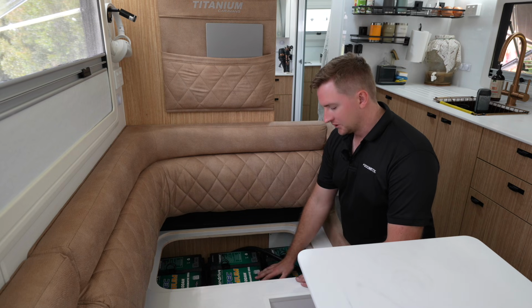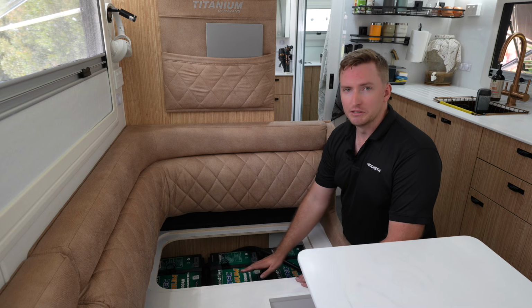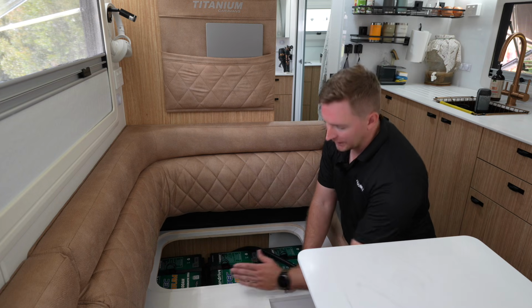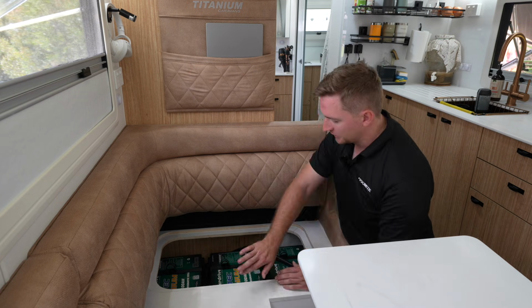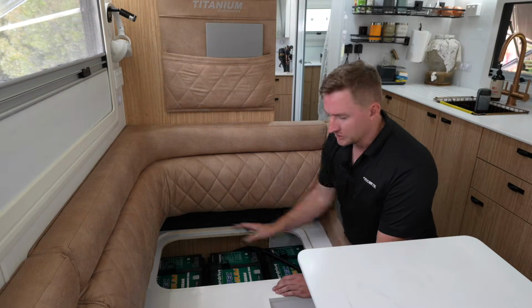This particular installation here is 3/4 of the way there. All that we need to do to make this completely compliant to the new standards is to ensure that we had a partition segregating our batteries that are on this side of this lounge space away from the rest of the electronics in this lounge space. We would have a lid that goes across the top here.